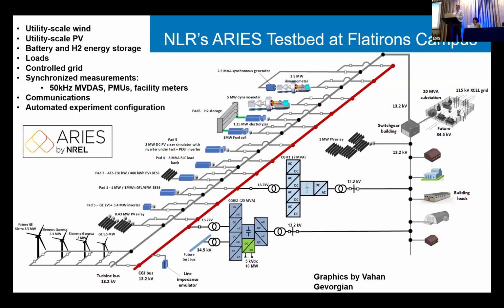But so we have the Xcel bus, and then we also have multiple what we call CG1 buses that allow us, on a separate medium voltage distribution system, to interconnect these assets. You can see the 2 grid simulators down there at the bottom. Probably a unique thing about our site is that not only do we have all these assets and multi-megawatt grid simulators, but we have the ability to connect an asset between 2 grid simulators. So it's perfect for doing this double conversion UPS validation.